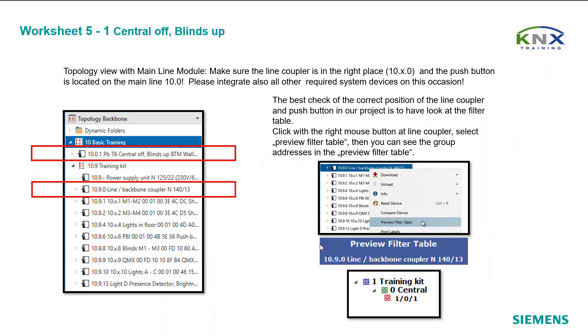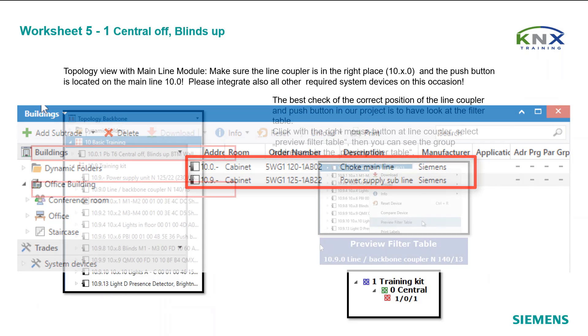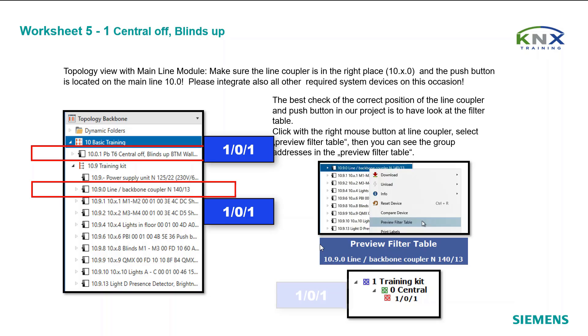Topology view with main line module: make sure the line coupler is in the right place, 10.x.0, and the push button is located on the main line, 10.0. Also integrate all other required system devices such as chokes and power supply units. The best check of the correct position of the line coupler and push button is to look at the filter table. Right-click on the line coupler and select 'Preview Filter Table' to see the group addresses. The filter table will show group addresses only if they have links to communication objects on either side of the line coupler.